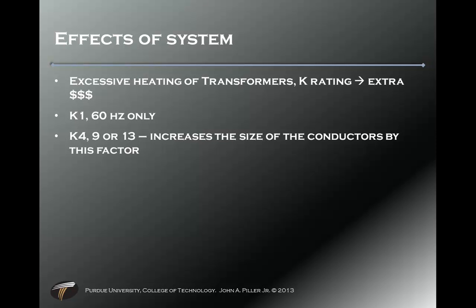Harmonics also cause excessive heating of transformers. There's a thing called a K-rating: as you increase the K-rating, you increase cost. If you only have linear loads, a K1 transformer is fine. But you could end up needing a K4, K9, or K13 — a multiplying factor — making the transformer four, nine, or thirteen times the size of a standard transformer, rated only as K1, with correspondingly increased cost.